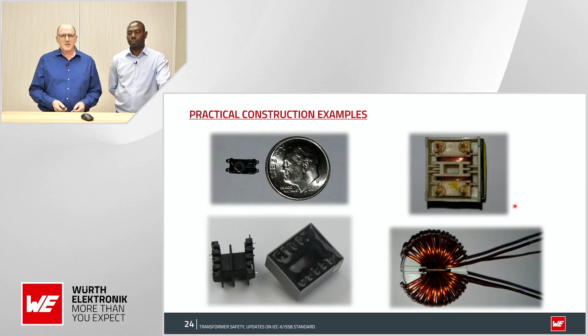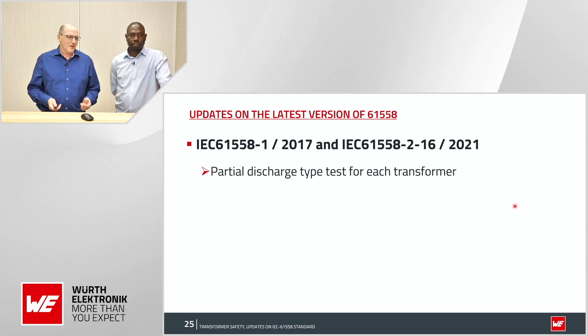We have in the 61558-1 and 61558-2-16 some news and updates. We have to test the partial discharge. It is a type test for each transformer, but please take care of this point, because in the -2-16 it is more or less written that all transformers need to test it, while in the -1 it's written that all transformers with triple insulated wire or FIW wire, with peak working voltage higher than 750 volt, need to be tested. So please take care and check with your test lab.